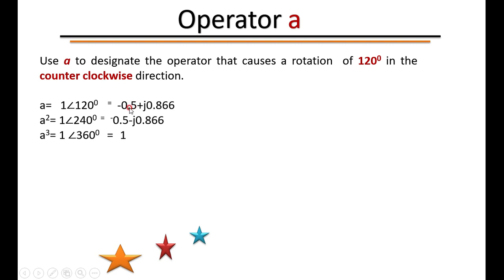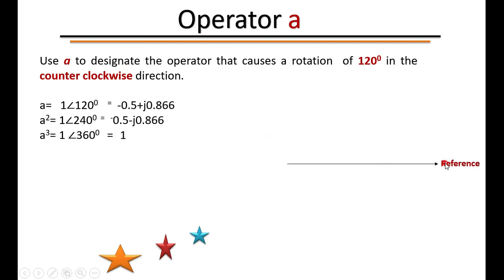Converting the operator 'a' = 1∠120° to rectangular form gives −0.5 + j0.866. If you operate 'a' twice on a vector, that becomes a², which is 1∠240°, with rectangular form −0.5 − j0.866. Operating 'a' three times gives a³ = 1∠360°, which equals 1∠0°, the reference vector — meaning it is back in phase with the reference.